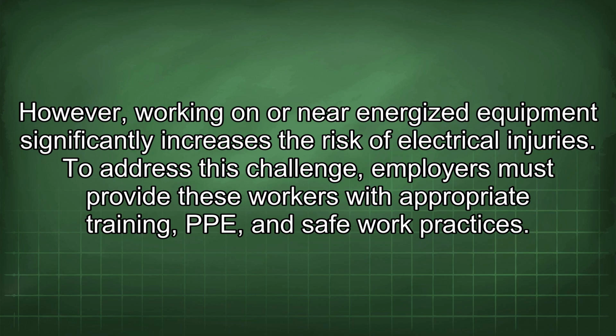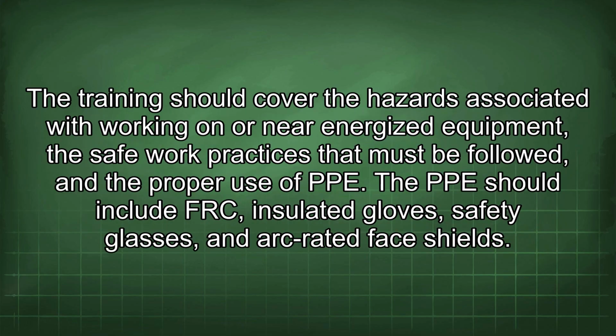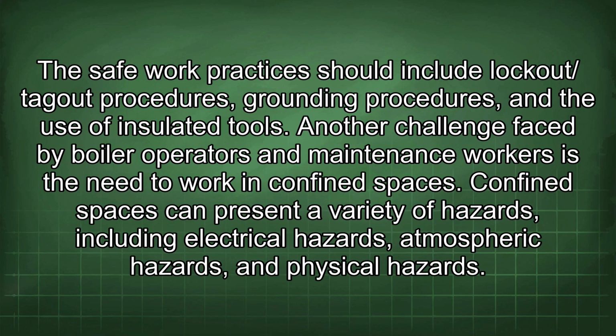To address this challenge, employers must provide these workers with appropriate training, PPE, and safe work practices. The training should cover the hazards associated with working on or near energized equipment, the safe work practices that must be followed, and the proper use of PPE. The PPE should include FRC, insulated gloves, safety glasses, and arc-rated face shields. The safe work practices should include lockout/tagout procedures, grounding procedures, and the use of insulated tools.